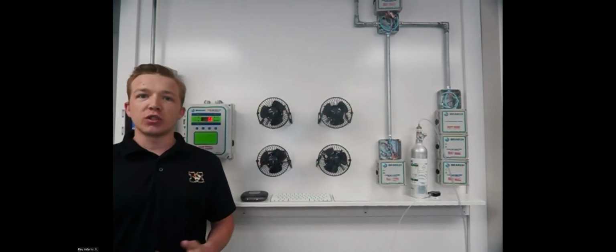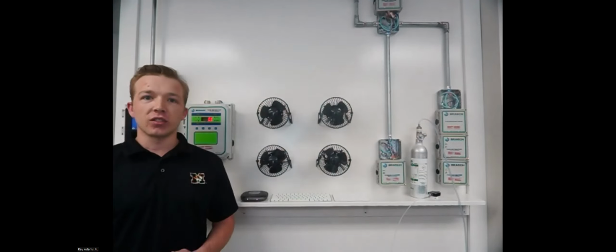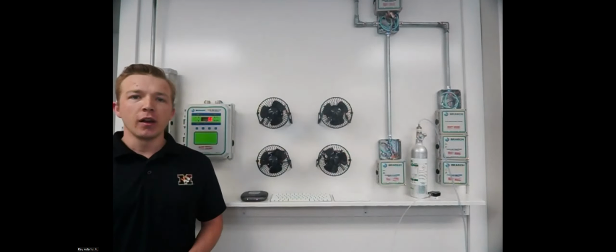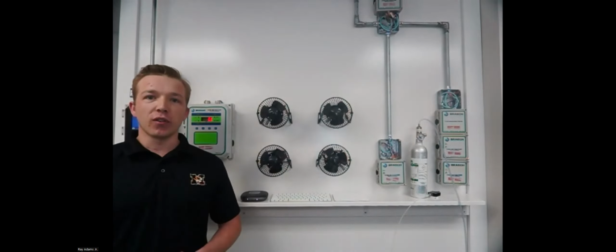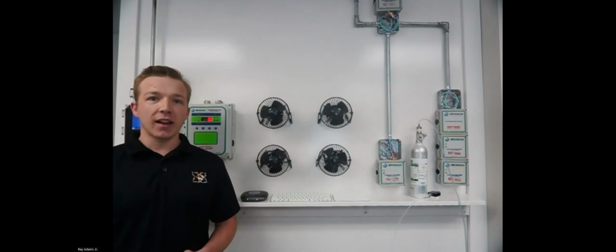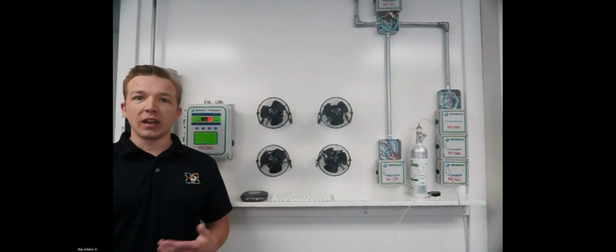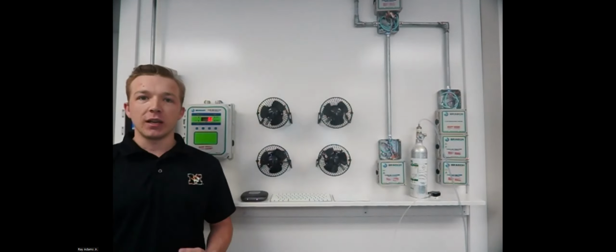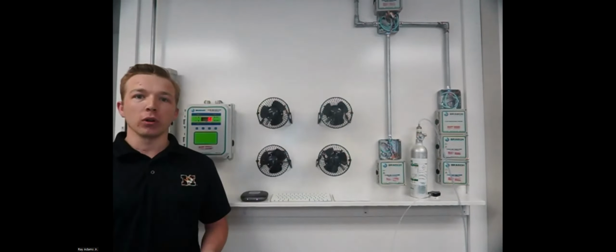Generally speaking, there's a dozen gas detection manufacturers out there, and for the most part all of the systems function in a pretty similar fashion. You're going to have a sensor that's detecting the gas, sending that signal back to some type of controller that's then going to turn on your ventilation equipment, open up a damper or louver to begin ventilating the facility to keep those gases under a harmful level.